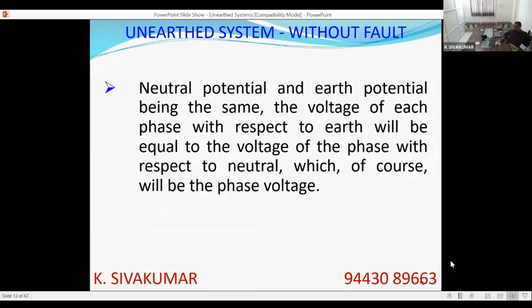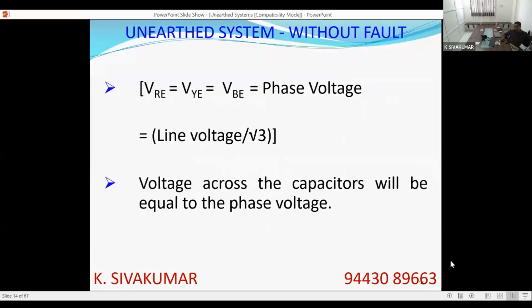The voltage of each phase with respect to earth will be equal to the voltage between phase and neutral. That is called the phase voltage. So now VRE = VYE = VBE = phase voltage, that is, line voltage by √3. The voltage across the capacitor will be equal to the phase voltage. Each phase-to-earth capacitor will have the phase voltage of the system impressed upon it.